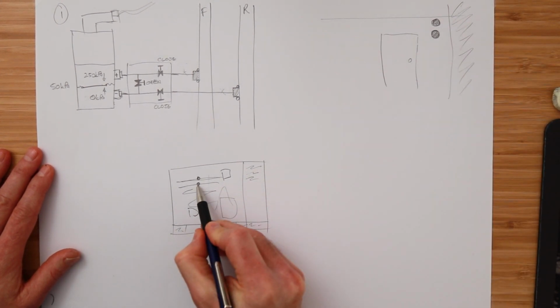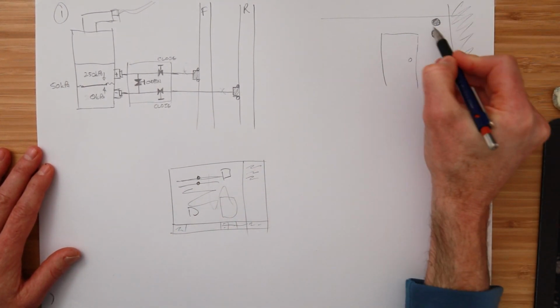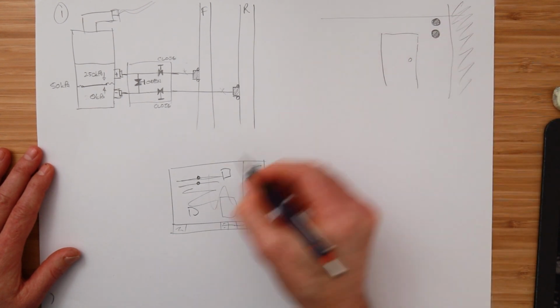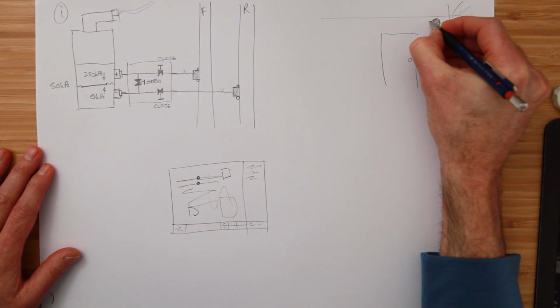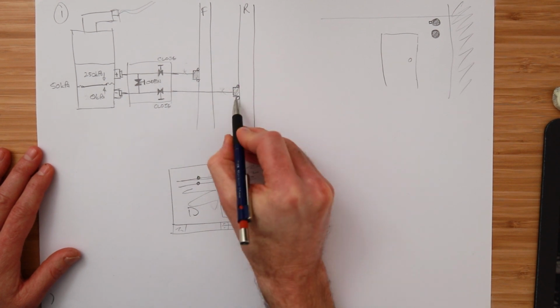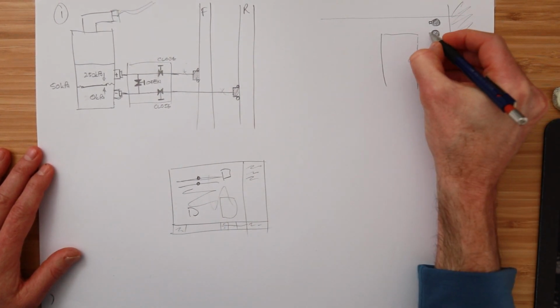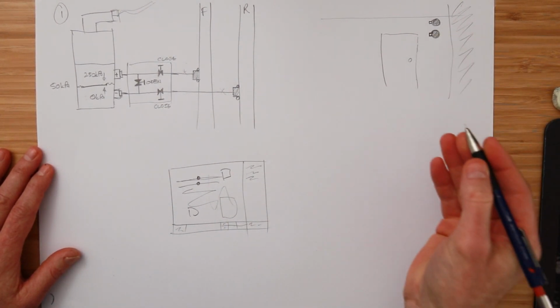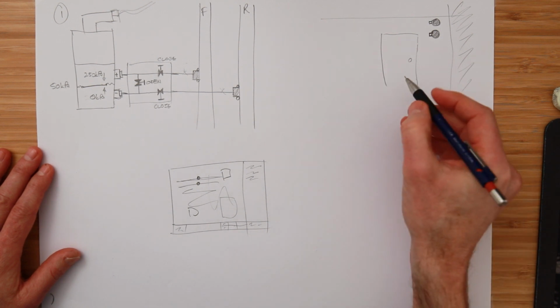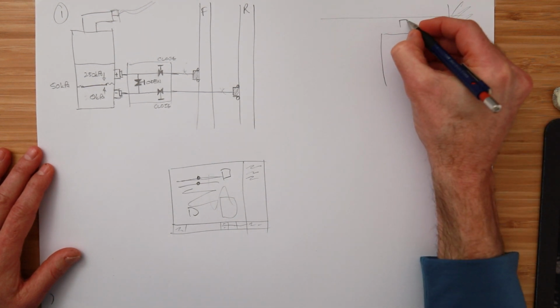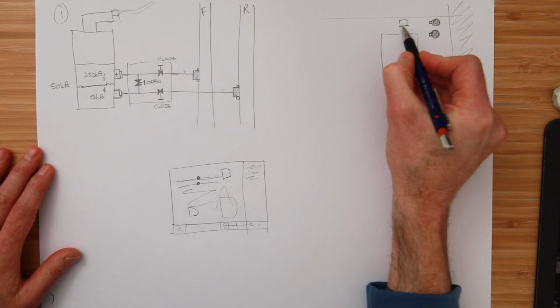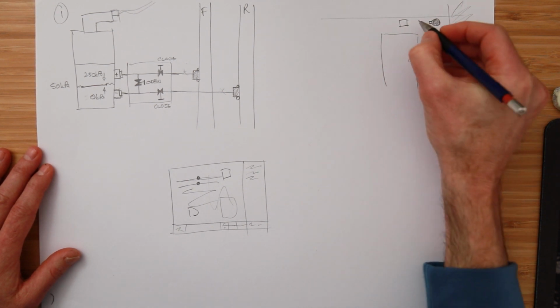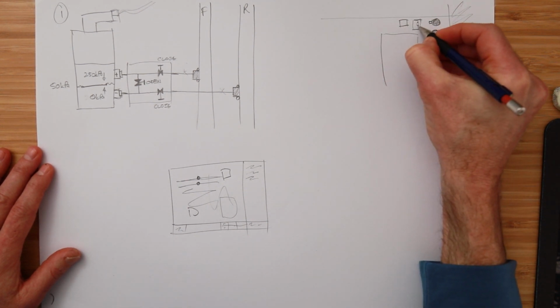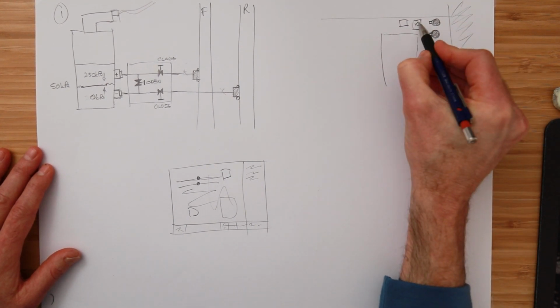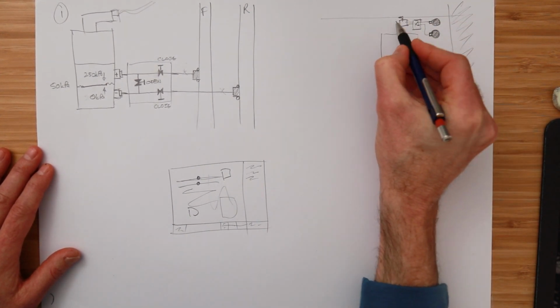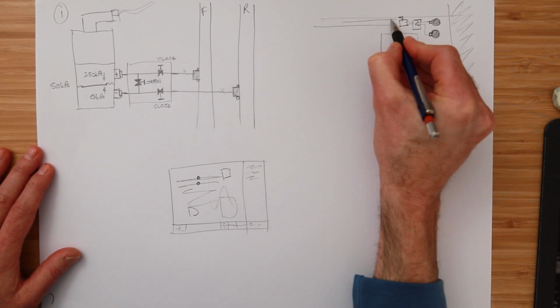And if in your schematic, that location happens to be right over here, then what will happen is the mechanical pipe fitter will weld that socket on over here, these two sockets. They'll get welded onto here. And what happens is your BMS installer is going to come here. They might install the transmitter up here on the wall. It's a good location. There's a bit of a wall there. They can screw on the plate, maybe the manifold with the 3 valves. Maybe it goes there, so that goes into the manifold like that. Cable comes along here. Bit of a containment route along here.